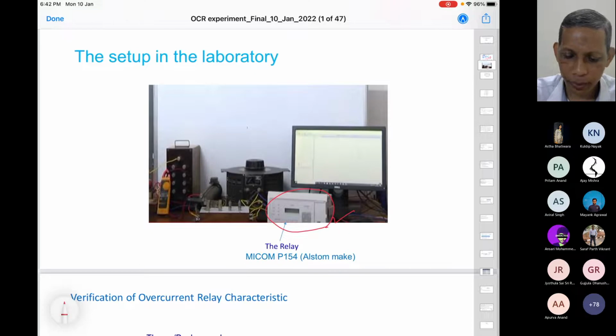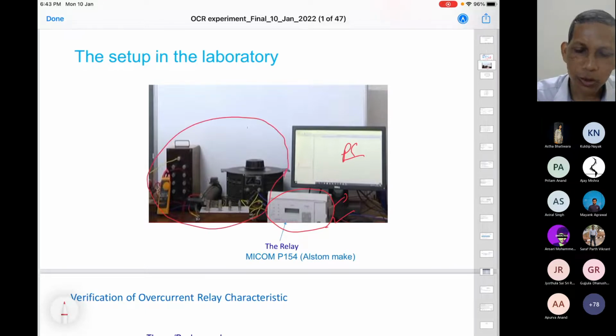Alstom make. We'll come to that. And it is a numerical relay. This device is connected to the PC. So we can connect to the PC for control, command, setting changes, data recovery, all things we can do through the PC. And then we have a setup arrangement to inject current to this device, because this is an overcurrent relay, so its input will be only current.